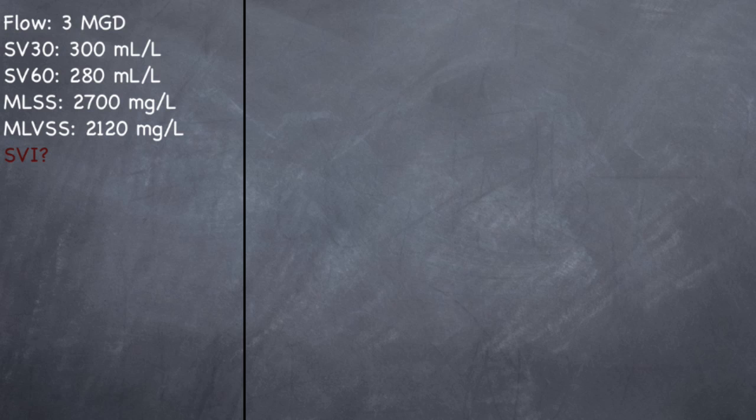The formula for that is your SV30 times 1000 divided by your MLSS milligrams per liter, and that will give you your SVI. I don't think they give you this formula on the cheat sheet, so it's important that you memorize this. Just write it down this way and memorize it that way, and you'll have no problem doing the problem when they give it to you.